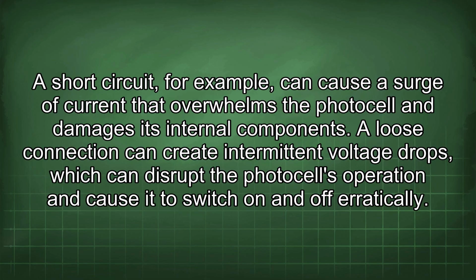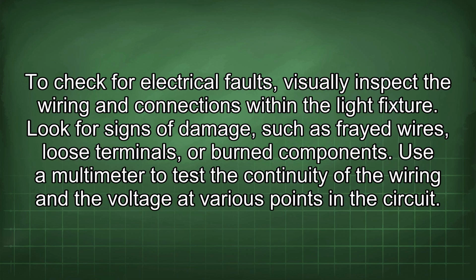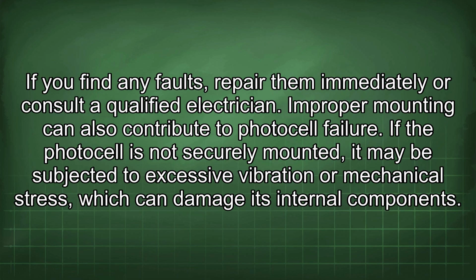A short circuit, for example, can cause a surge of current that overwhelms the photocell and damages its internal components. A loose connection can create intermittent voltage drops, which can disrupt the photocell's operation and cause it to switch on and off erratically. To check for electrical faults, visually inspect the wiring and connections within the light fixture. Look for signs of damage such as frayed wires, loose terminals, or burned components. Use a multimeter to test the continuity of the wiring and the voltage at various points in the circuit. If you find any faults, repair them immediately or consult a qualified electrician.